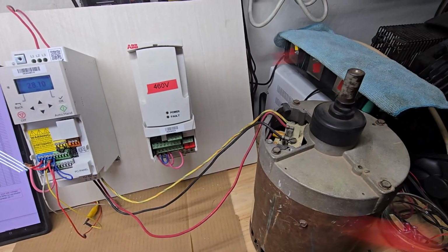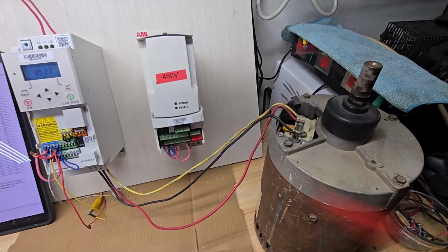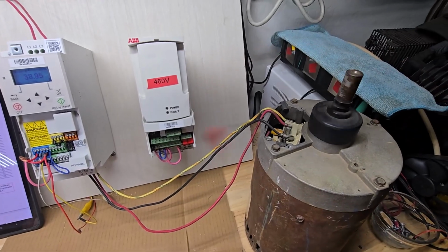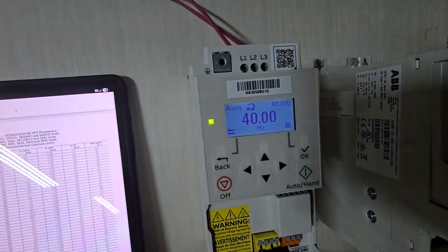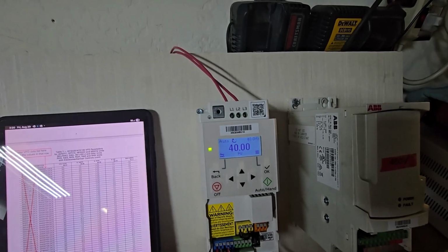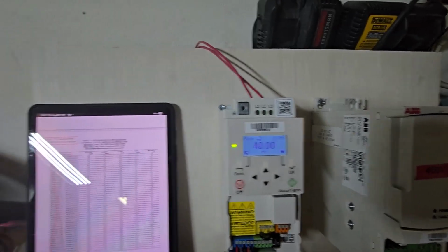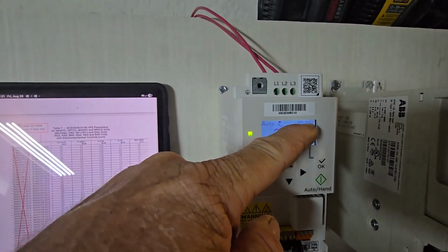And when you have all that inertia you're getting going, this is called a soft start, which is actually good. Saves on the belts, saves on the noise, just more efficient. And there we go, getting up to 40 hertz. And then what the drives do is, when you get a call for that second stage cooling, the relay board is going to switch to this other input instead. Now it's calling for 60.